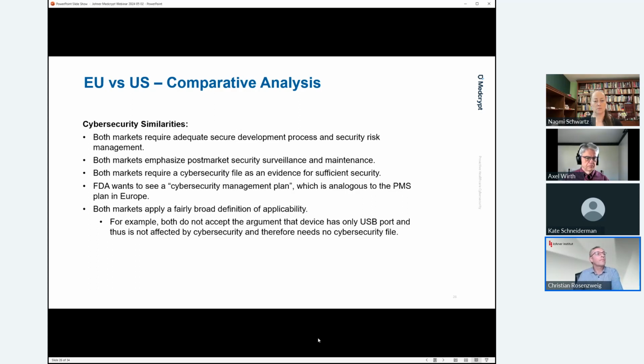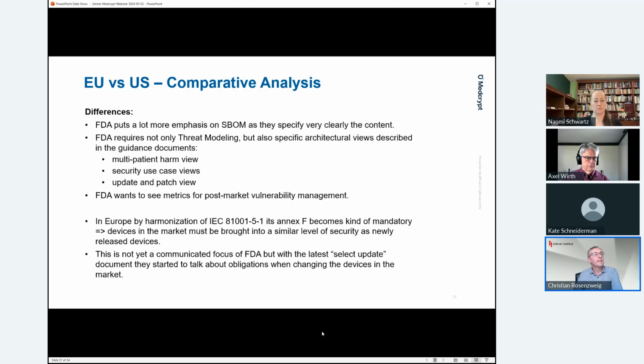Okay. Next slide. FDA, what are the differences? FDA puts a lot more emphasis on the SBOM, the software bill of materials, because they specify exactly what the content of that SBOM is. Naomi already mentioned the NTIA specifications, the baseline attributes that should be used for that, and FDA specifies additional requirements for the SBOM in the guidance document.